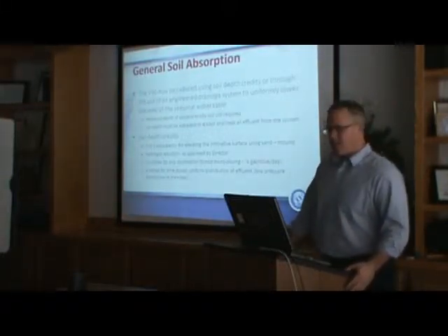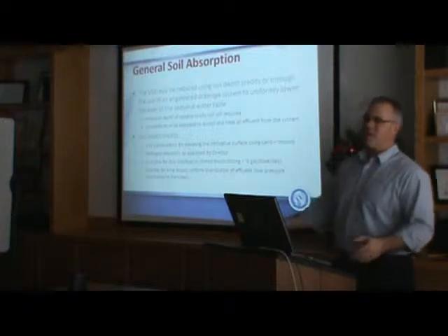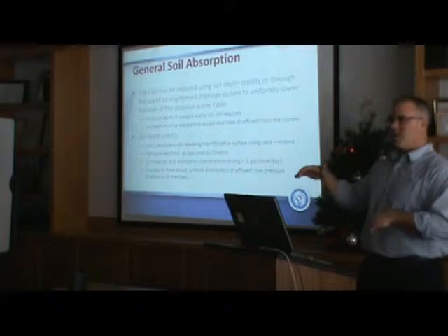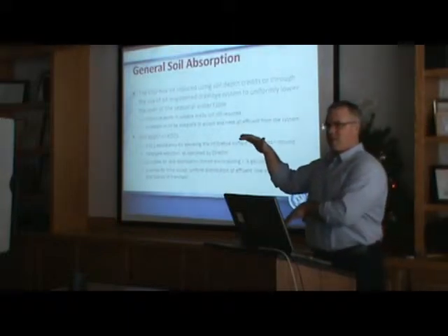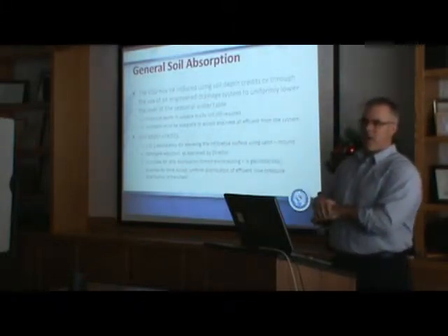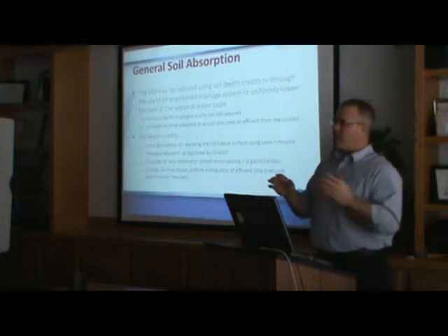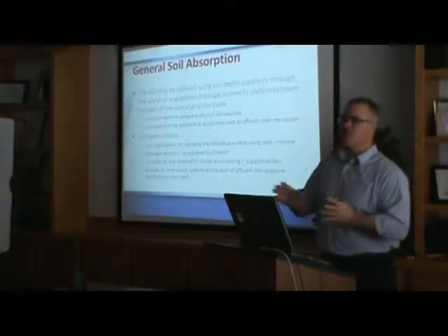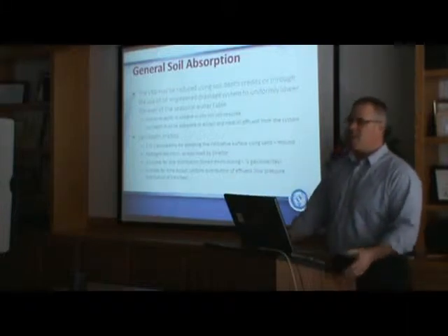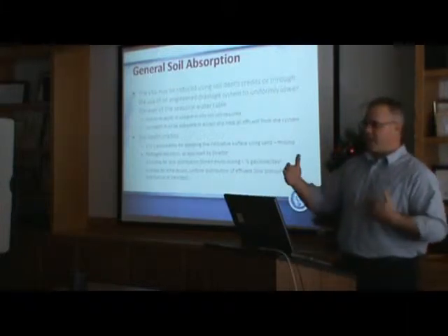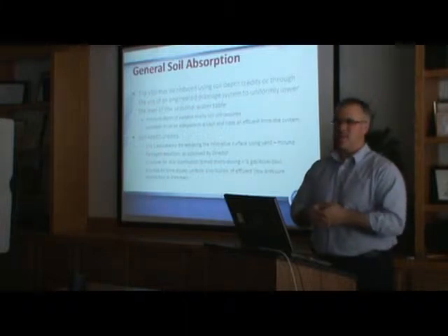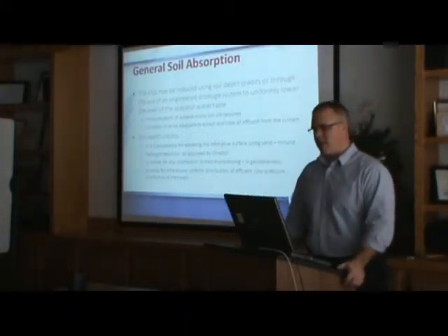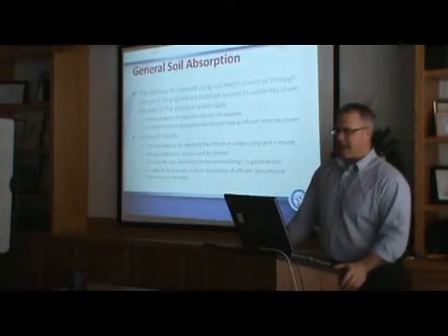All right, vertical separation distance. So we talked about the vertical separation distance and the minimums that we're going to see. We're going to see an 18-inch default, 36 inches for groundwater and bedrock, and probably 12 for seasonal perch water table. So here are things you can do to get closer to that. And this is a principle we saw in 2007. We're using it right now, but the same types of ideas.